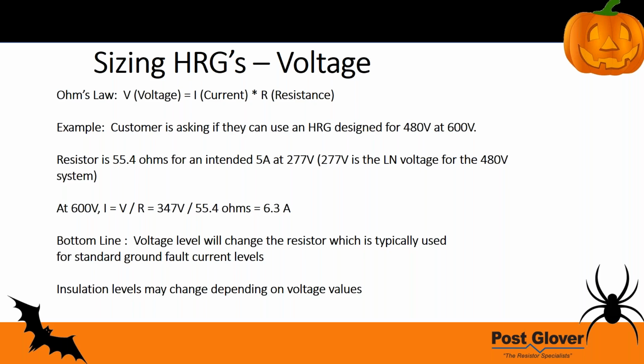As an example, a customer asks if they can use an HRG designed for 480 at 600 volts. This actually happens a few times a year—the purchaser makes a mistake, probably puts down 600 volts, and most of the time people just assume that means 480 volts. Sometimes it doesn't, and so you end up with a wrongly designed HRG.